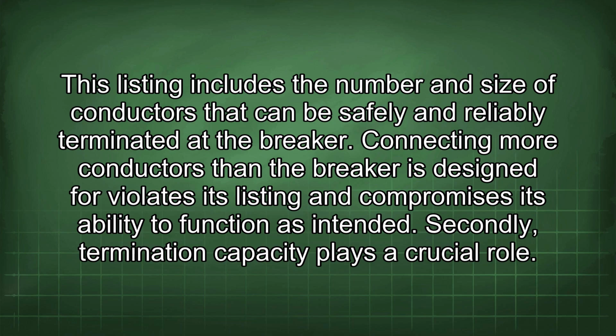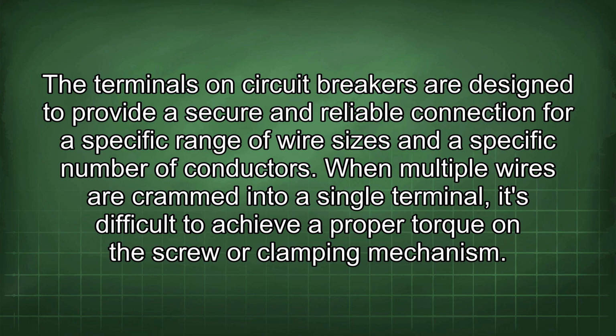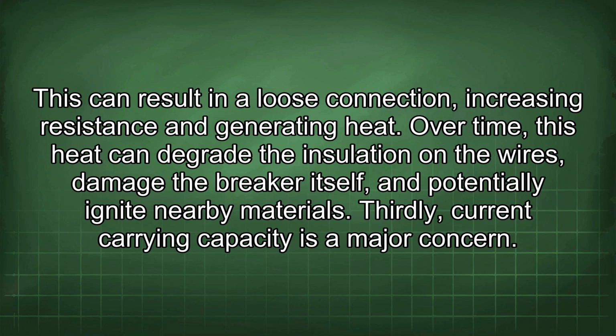Secondly, termination capacity plays a crucial role. The terminals on circuit breakers are designed to provide a secure and reliable connection for a specific range of wire sizes and a specific number of conductors. When multiple wires are crammed into a single terminal, it's difficult to achieve proper torque in the screw or clamping mechanism. This can result in a loose connection, increasing resistance and generating heat. Over time, this heat can degrade the insulation on the wires, damage the breaker itself, and potentially ignite nearby materials.